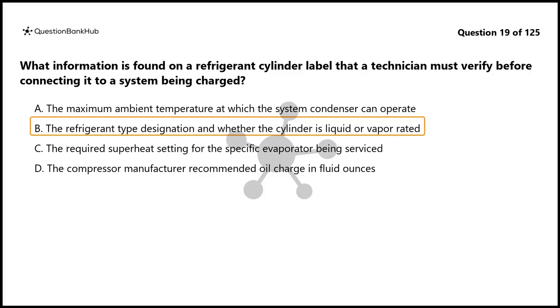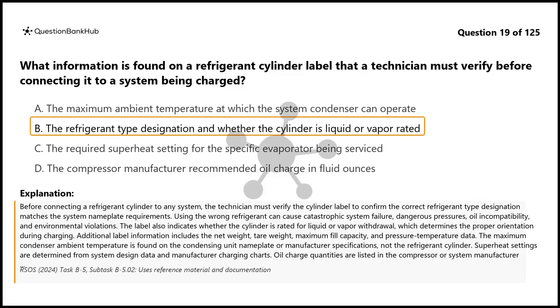The correct answer is B. Before connecting a refrigerant cylinder to any system, the technician must verify the cylinder label to confirm the correct refrigerant type designation matches the system nameplate requirements. Using the wrong refrigerant can cause catastrophic system failure, dangerous pressures, oil incompatibility, and environmental violations. The label also indicates whether the cylinder is rated for liquid or vapor withdrawal, which determines the proper orientation during charging. Additional label information includes the net weight, tare weight, maximum fill capacity, and pressure temperature data.